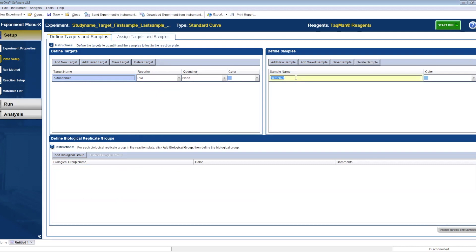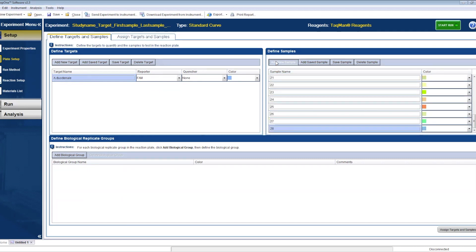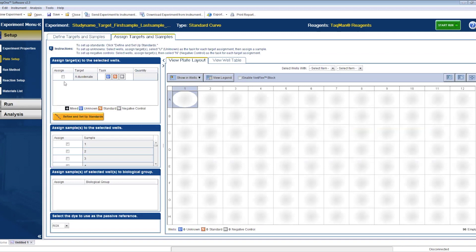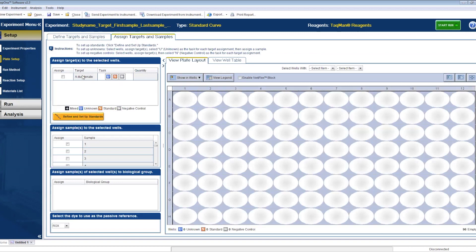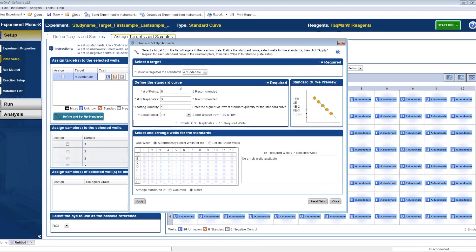There is a way to load the sample order automatically - we'll share this way in the SOP - but you still need to assign the samples to the wells manually. Choose the tab Assign Targets and Samples, highlight the entire plate layout, and click and assign the target of choice.